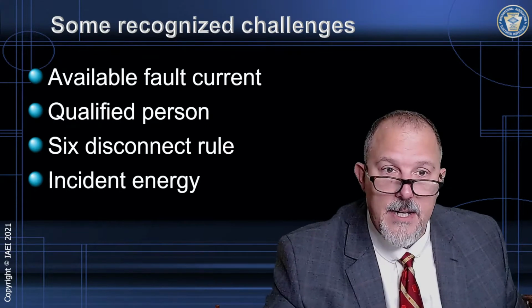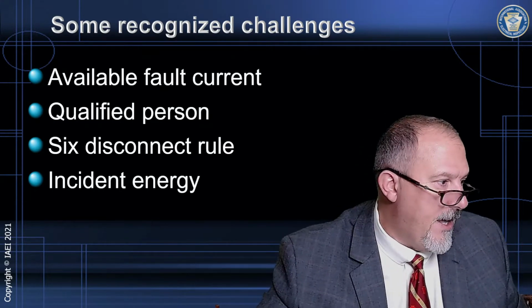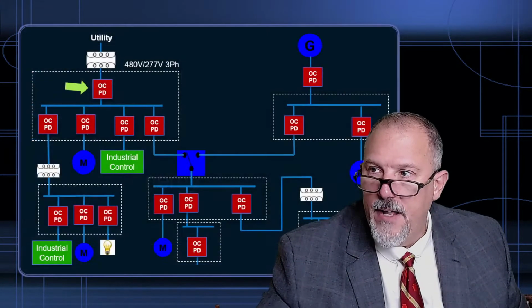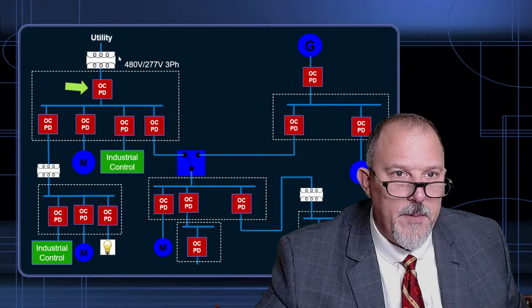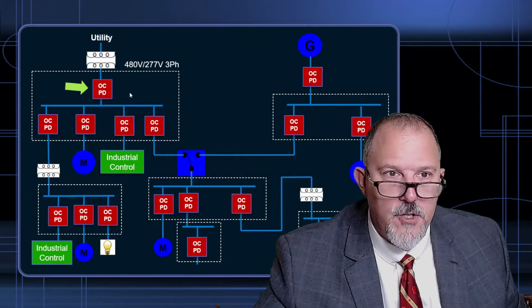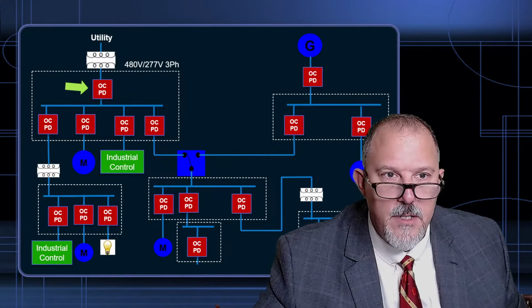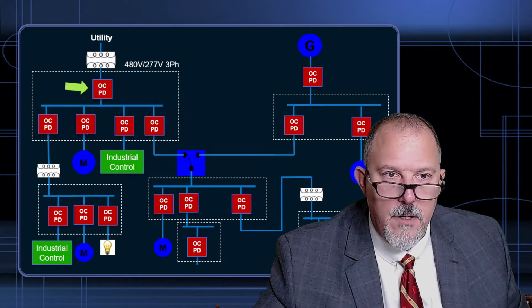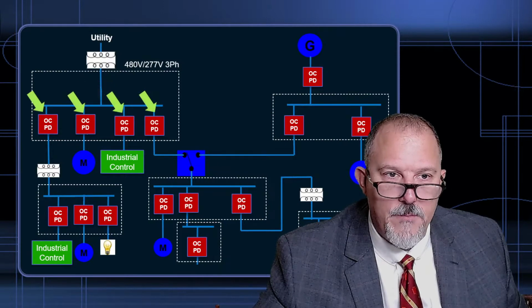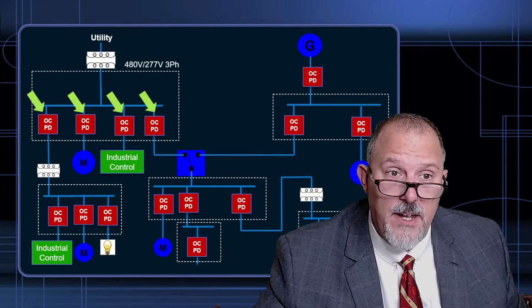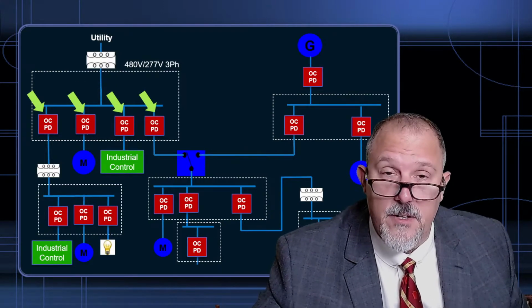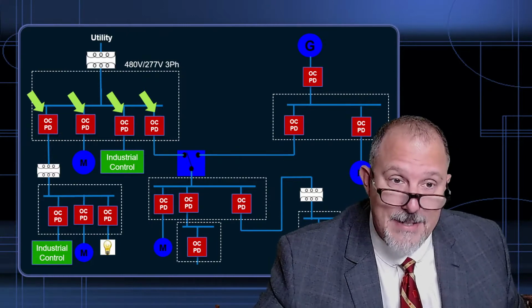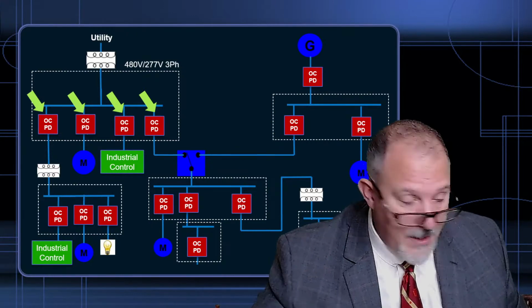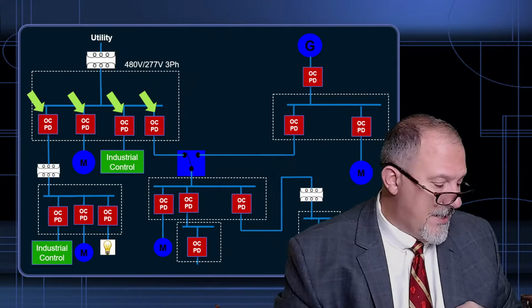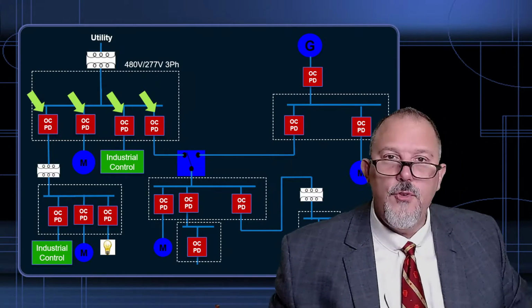The 6 disconnect rule. What happens if this is my equipment up here and I have a main overcurrent device? Well, the clearing time is easy to find out. But if I don't have that, and I'm doing a 6 disconnect rule, I could have up to 6 different clearing times. Does that make sense? And then the discussion was, wait a second, who's going to use this?